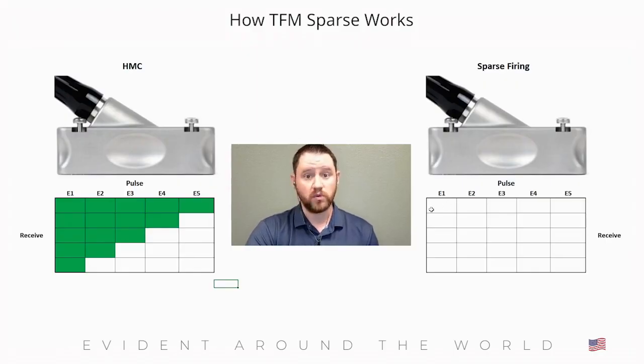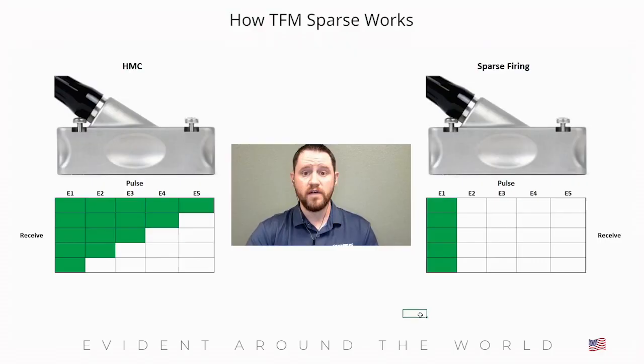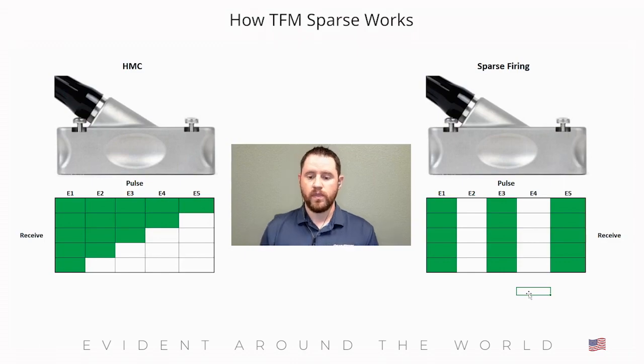So let's say, for example, we start with element number 1 and that pulses, and we'll highlight these cells to simulate that we've received on that pulse. In the next sequence, normally we would fire element number 2, but in this case, in sparse mode, we choose to skip the pulsing of element 2 and go straight to element number 3. So then we pulse with element number 3, listen with all of the other elements of the transducer, and there we have our next data set. And then we repeat that process until we reach the end of the transducer. So by firing fewer elements of the transducer, that also creates less data for the instrument to have to manage, and that should give you a boost in the inspection speed.